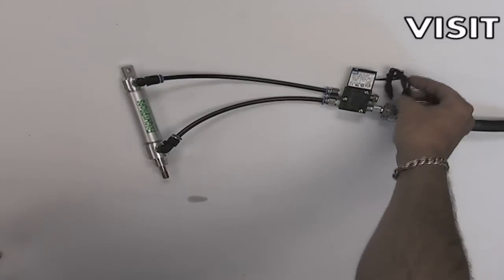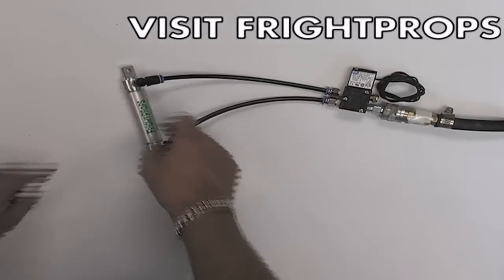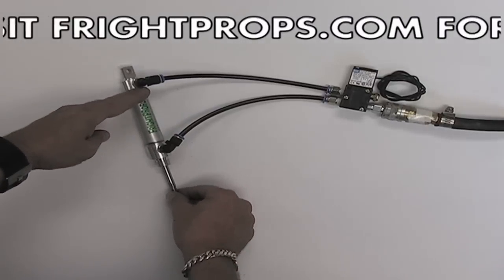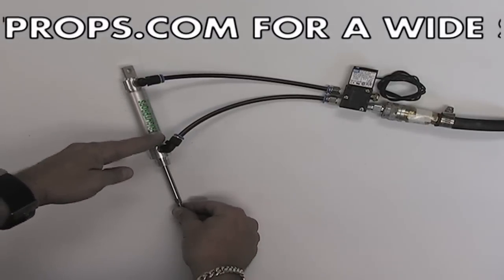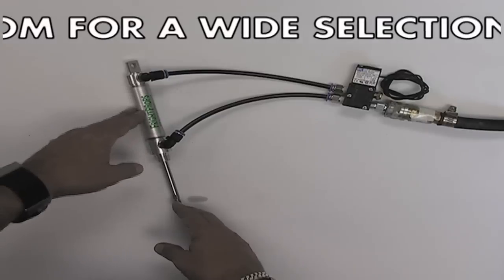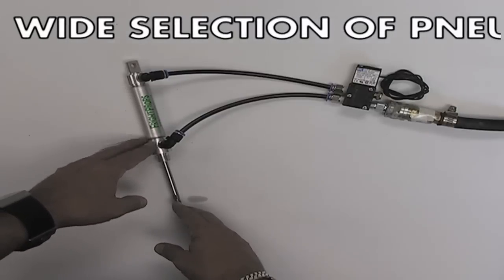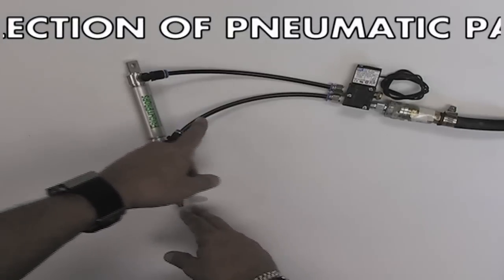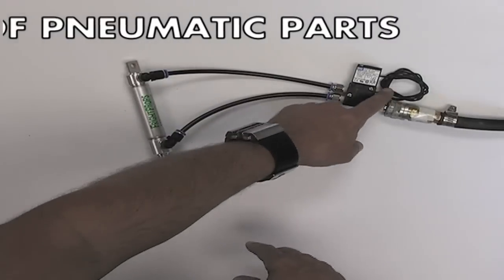When you energize the solenoid, air is going to push to the bottom, pushing the shaft out with air. And the displaced air that's being pushed in front of the piston is going to come back down this air line and come out of the exhaust.